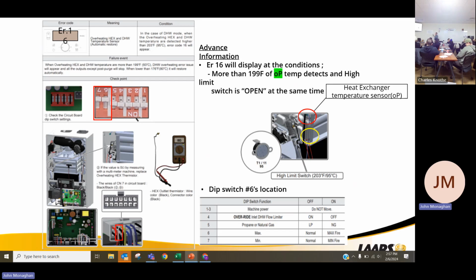Error 16, I've got to fix that. Kind of out of space, but that's your high limit. It overheated. Causes for the overheat: dirty heat exchanger, plugged up heat exchanger. If it's filled with calcium and other buildup, we're not transferring or absorbing the heat, which will cause that limit to switch. That's where we would flush the unit. That's where you get your flush kits. You'd use whatever, your citric acid, your vinegar, to clean any of that debris out of that heat exchanger.